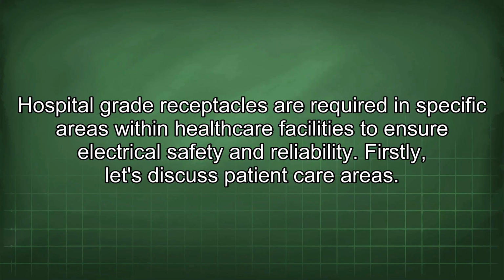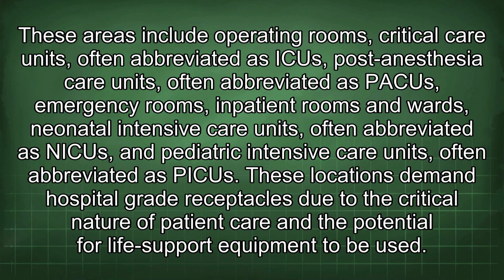Hospital-grade receptacles are required in specific areas within healthcare facilities to ensure electrical safety and reliability. Firstly, let's discuss patient care areas. These areas include operating rooms, critical care units, often abbreviated as ICU, post-anesthesia care units, often abbreviated as PACUs, emergency rooms, inpatient rooms and wards, neonatal intensive care units, often abbreviated as NICUs, and pediatric intensive care units, often abbreviated as PICUs. These locations demand hospital-grade receptacles due to the critical nature of patient care and the potential for life support equipment to be used.